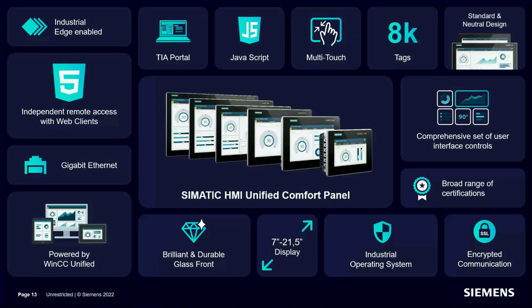Some information around the core Comfort Panels configured in TIA Portal: they have JavaScript capabilities, multi-touch, typically 8,000 tags, and standard and neutral designs. They have a comprehensive set of user interface controls which are standard across all the different hardware or software platforms, plus a broad range of certifications - earlier this year, around February, the units became compliant with ATEX Zone 2/22, DNV and Lloyd's shipping approvals. These are great standards that mean these panels can be used in lots of different applications.